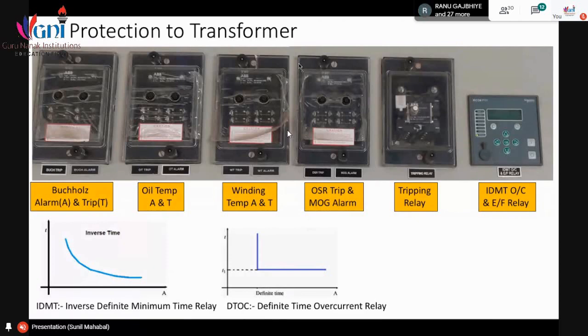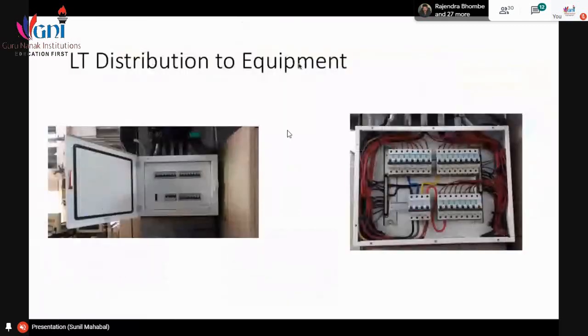So even if the break fault current is more, it will take the same time. So it is definite time over current relay, DTOC. Then it goes to LT distribution to equipment, through these MCBs. So the miniature circuit breaker works.